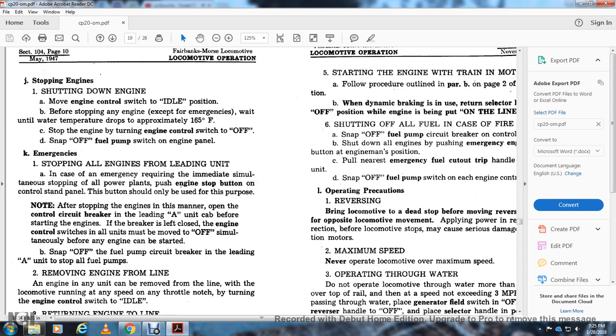Note that after stopping the engine, this will open the control circuit breaker in the leading unit cabinet before starting the engine. If the breaker is left closed, the engine control switches in all the units must be moved to the off position simultaneously before any engine can be started. B. Snap off the fuel pump circuit breaker in the leading unit, which stops all the fuel.